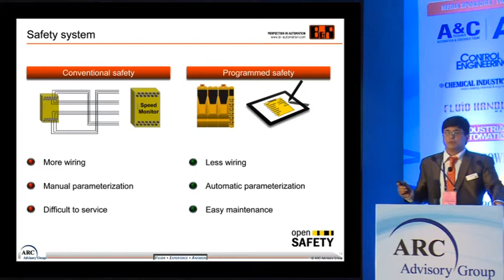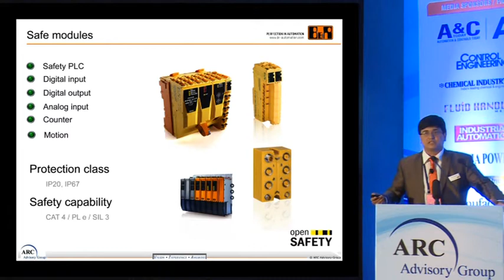We can propose a programmable safety solution, which has a safety controller along with software-programmed safety, which can reduce your wiring effort and give automatic parameterization of the components. So once you replace a safety component with a similar safety component, you don't need to program it again. It just gets parameterized automatically. Plus, as they seamlessly integrate onto the bus, all the diagnostics and maintenance of these components can be easily done. When we talk about safety, what we get today are safety controllers, digital input, digital output, some analog input, analog output, counter modules, and some motion components, which completely give you the highest level of safety.